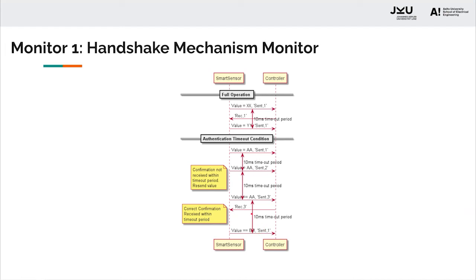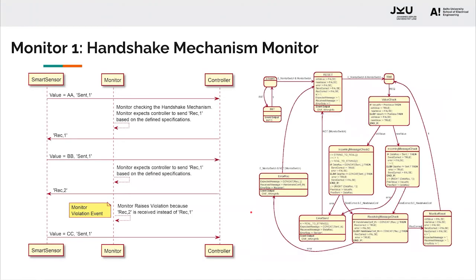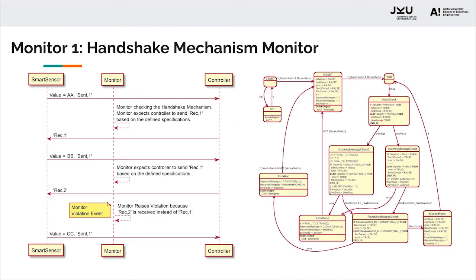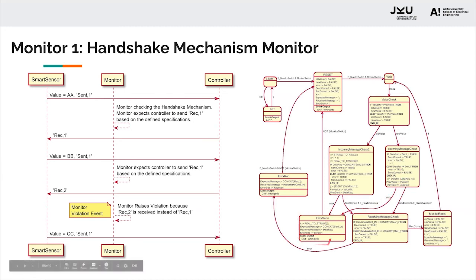How do we monitor this? We have a defined state machine. As soon as the value is sent from the smart sensor to the controller, the monitor picks up the value. Once it picks up the value, it checks if it's a new value or the old value. If it's an old value, it checks what message ID should be there. Should it be one or should it not be one? Because it's an old value, it will not be one. If it's a new value, it's one. This is how it checks the incoming message. If it finds an error, it comes to the state error in which the HMI is notified.